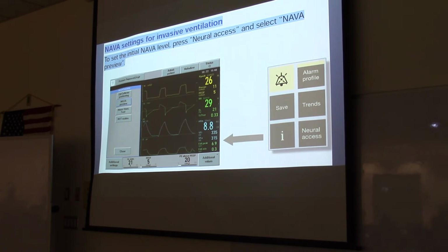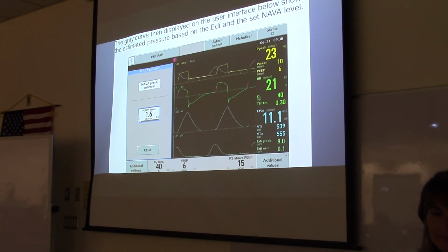All right, to set your initial Nava level, you press neural access on the ventilator. You'll see it over on the right. It'll say neural access right under trends. And then this screen comes up. And then you select Nava preview. And you will see, where's our, maybe it's on the next one. Looking for a gray, here we go. You're going to see an extra waveform, and it's the color of gray, and it shows when the pressure support is actually being delivered, if you have Nava turned on. And you can see some asynchrony, how it looks here like the breath is beginning well after the diaphragm received its innervation.